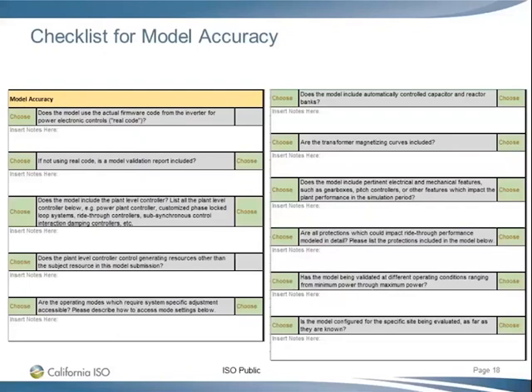The operation modes which require system-specific adjustment, are they accessible? Typically in the plant, the manufacturer will let you choose one of the operating modes. For example, for the Q control, you can do Q control, power factor control, or voltage control. So those modes should be accessible to you, and you already made that adjustment to match your plant. You just tell us if you have done that, and for this one, the answer should be yes.